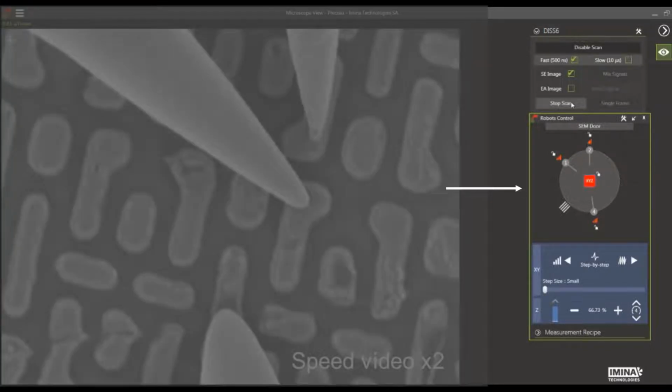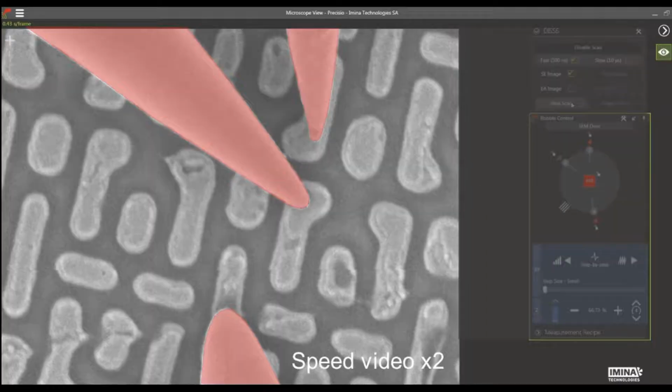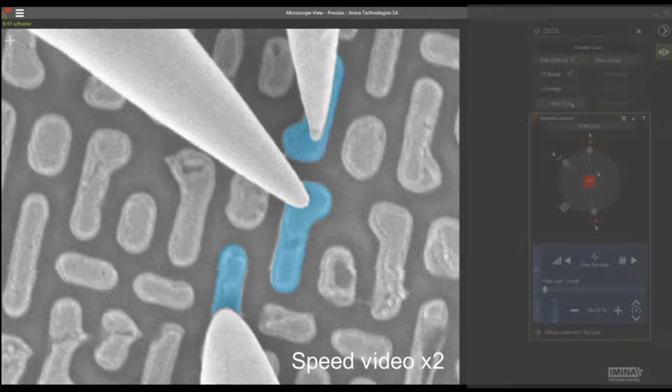This panel here is the nanoprobers and substage control unit. The red color marks the probing tips. The blue color marks an NMOS transistor from a 65 nanometer process, which we will be measuring here. This transistor from the SRAM area is delayered to metal 1.